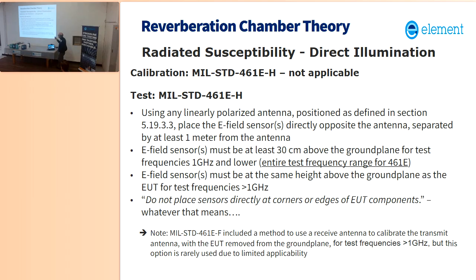461, you use any kind of linearly polarized antenna. Field sensor placement is 30 centimeters above the ground plane up to 1 gigahertz, and then next to the EUT for frequencies above 1 gigahertz. Then they've got this statement about do not place sensors directly at corners or edges of the EUT or components. But where else are you going to put them if it's not at the edges of the EUT? Because you're supposed to place the field sensor near the EUT. That's another talk. I'll be happy to give that later.